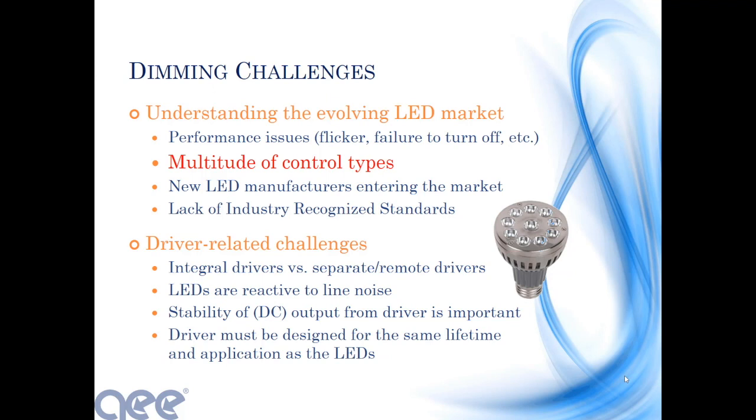So initially things come out, 100,000 hours, you really only have 40,000 hours, and by the way, you can't replace this 40,000 hour piece, so you have to replace your whole fixture, right? I'm in sales, I get why you do it, but it's not in the best interest, not truth in advertising, let's say. Okay, so that is another piece where you have to match those things up. The driver life is usually the lower life item in the fixture.